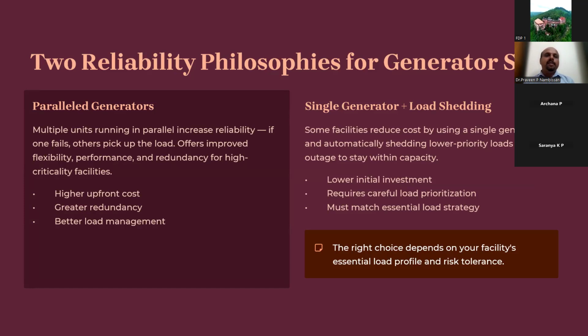The other approach, single generator plus load shedding, reduces cost by using a single generator and automatically shedding lower priority loads during an outage to stay within capacity. If capacity is insufficient, it load sheds automatically during generator operation, resulting in a comparatively lower initial investment.